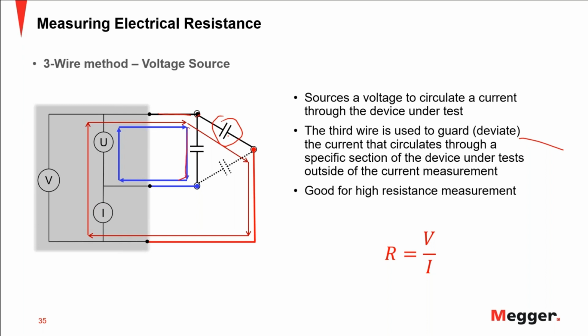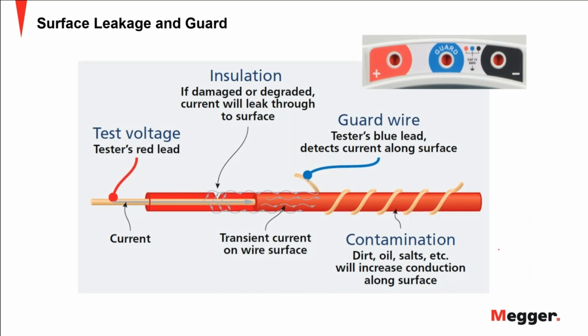This terminal or connection is called the guard conductor, and it helps you to deviate the surface leakage that could happen in some conditions. Let's say you are testing a set of panels or a conductor, and all of this is wet. When I apply the voltage here, yes, I may have some current flowing to ground through a fault, but I can also have a current flowing through the surface, and really this current on the surface is not the one that I'm interested in.